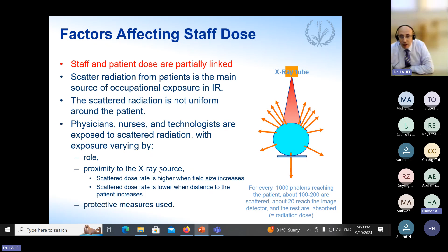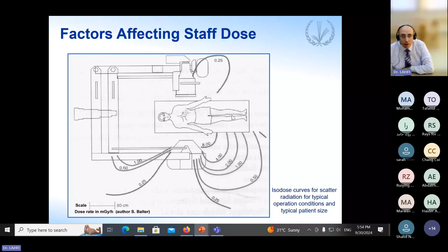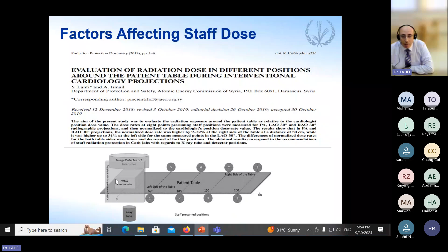This is the isodose curves for scatter radiation for typical operating conditions and typical patient sizes. This is a well-known figure. Also, we did a study in 2020 about the evaluation of radiation doses in different positions around the patient table during interventional cardiology projections for several IR systems. We measured the doses at 8 points, and we noticed that some points have low or higher staff doses according to the normal position near the shielding plate here.